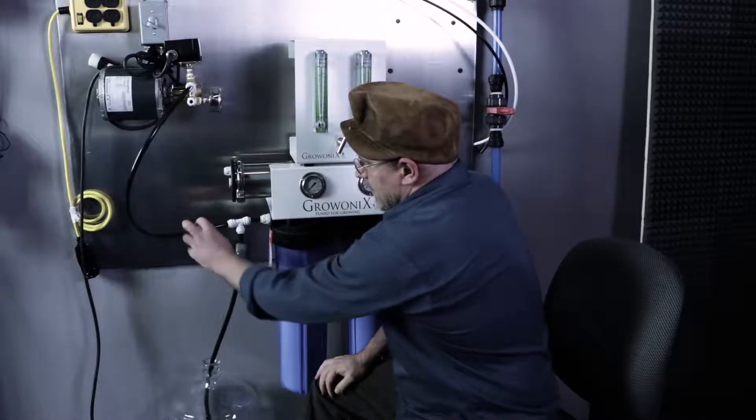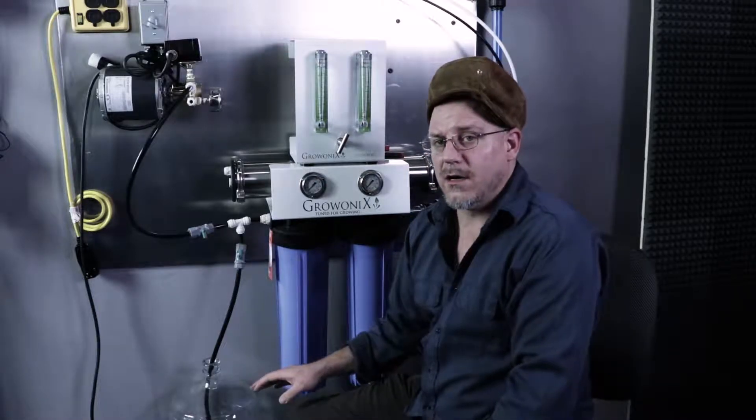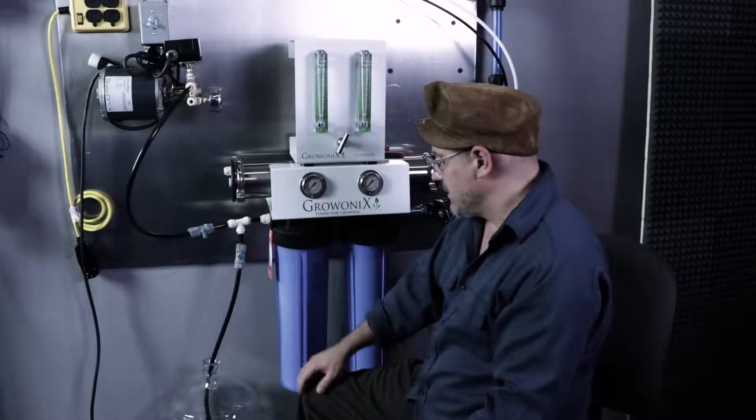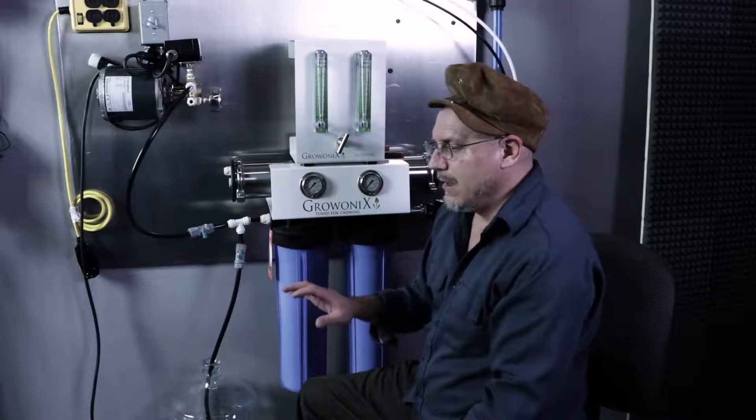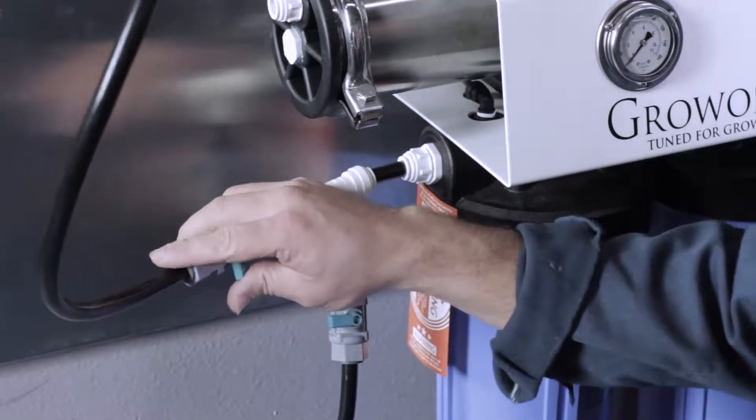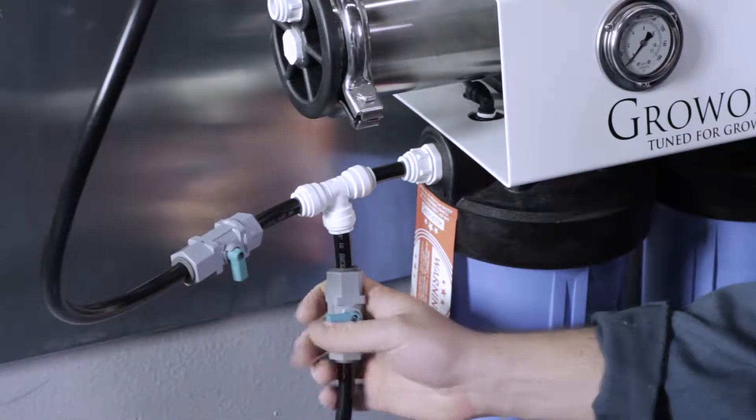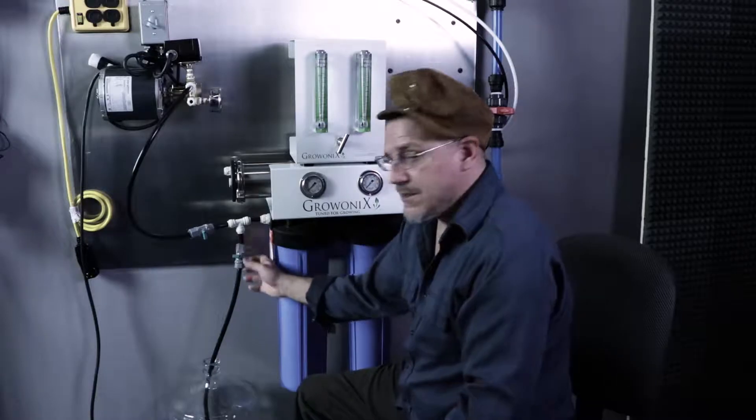So leave this valve closed, leave this one open, flush your carbon. When this water is clear, about 30 gallons of water. You could go up to 40 gallons of water with these talls until they get clear. And we're going to do that for you. And when it's done, we'll just close this valve and open this one and get ready for normal operation. But let's finish plumbing up the unit first. So let's flush that carbon right now.